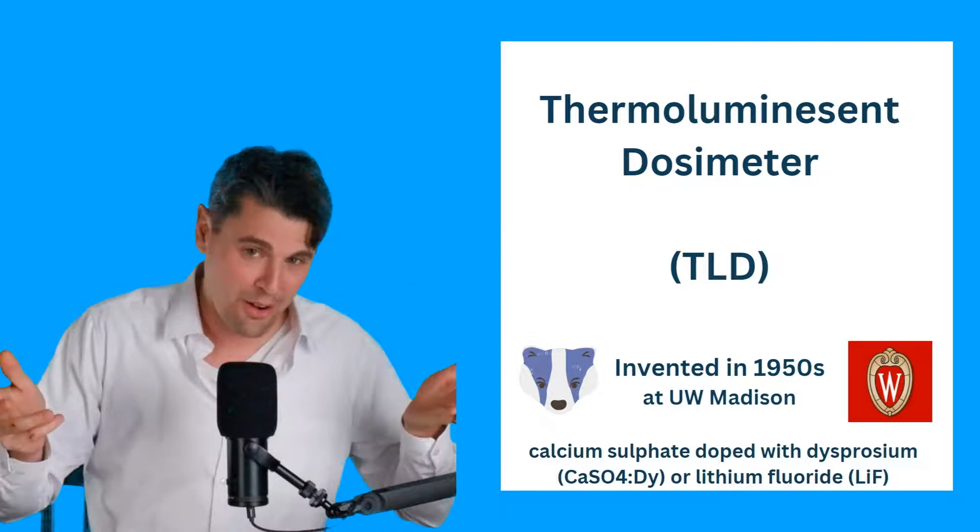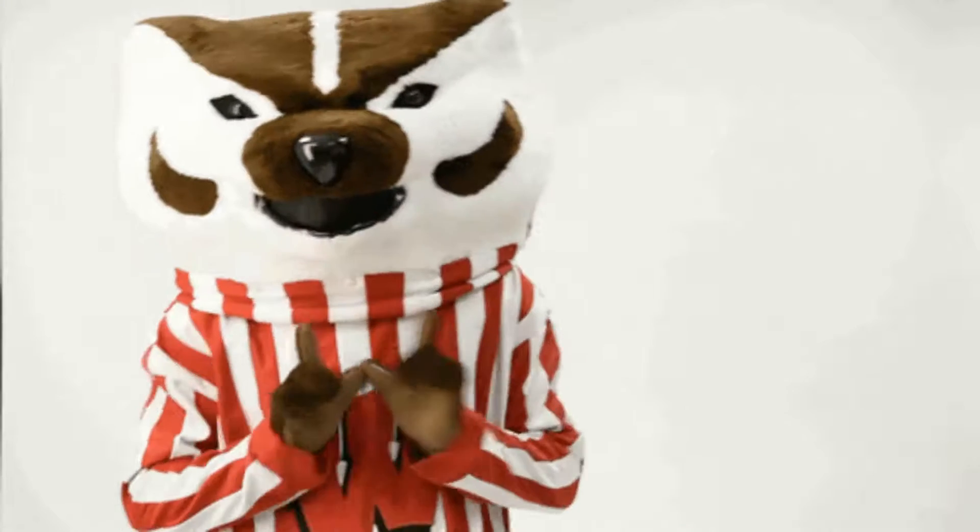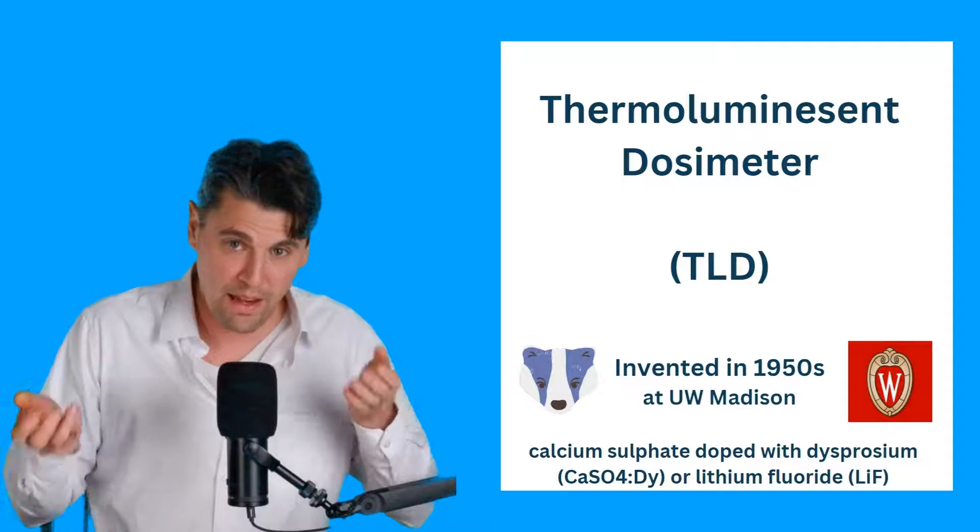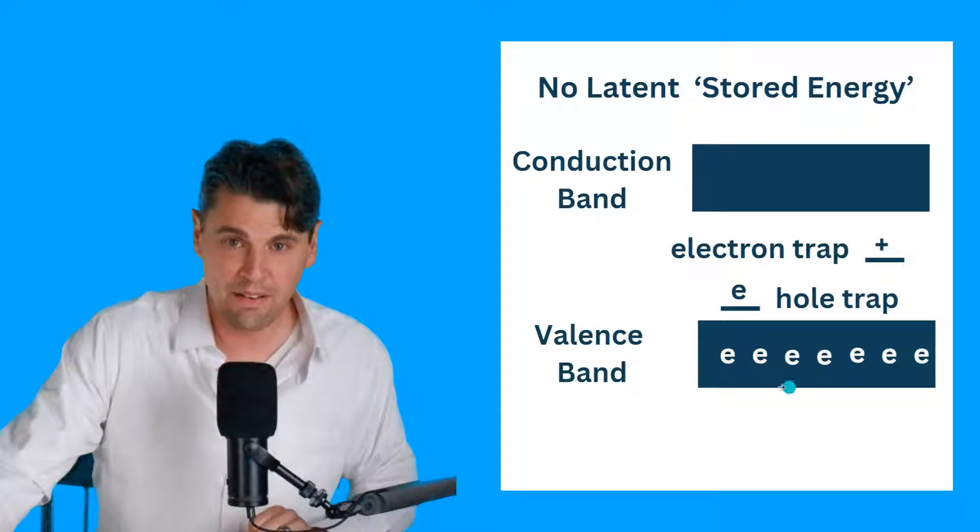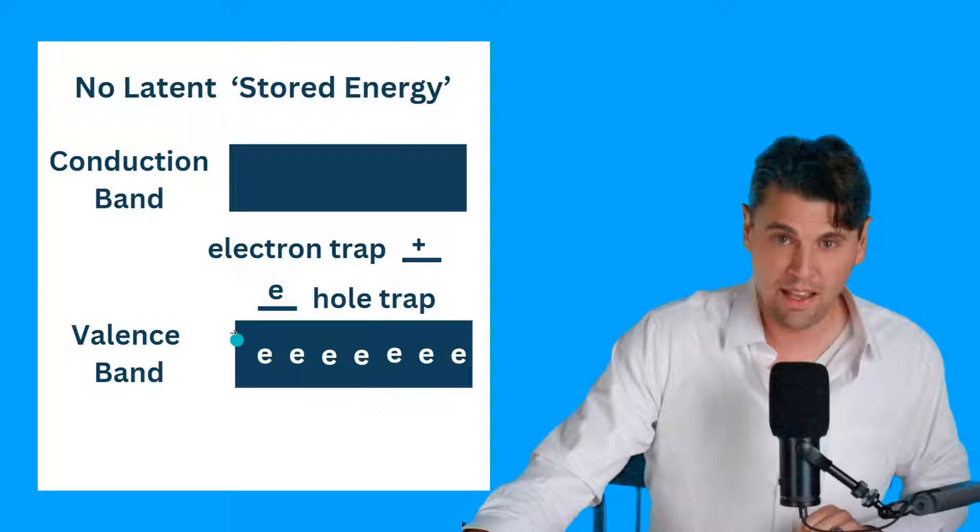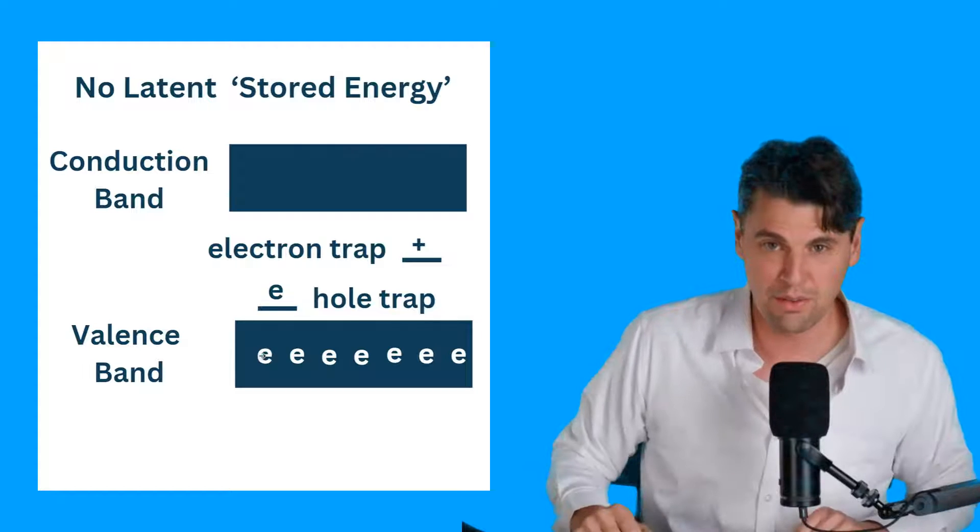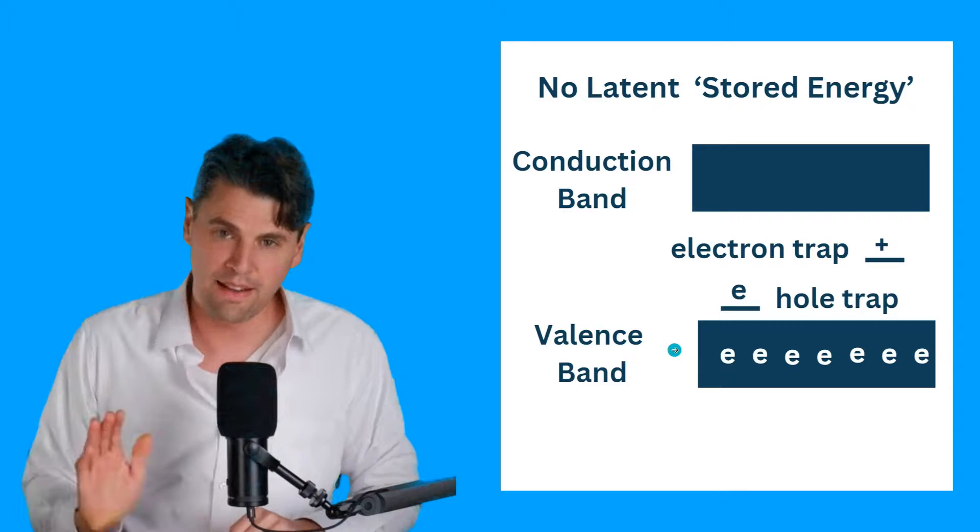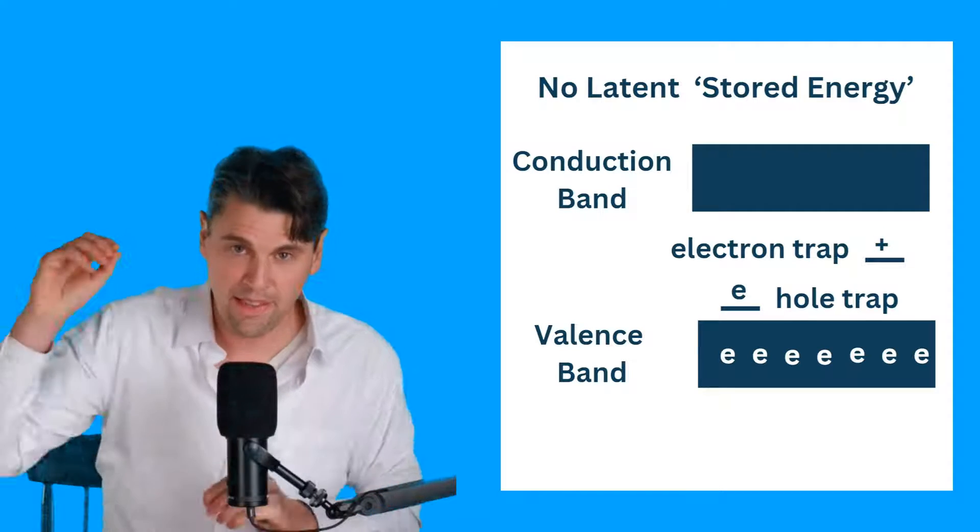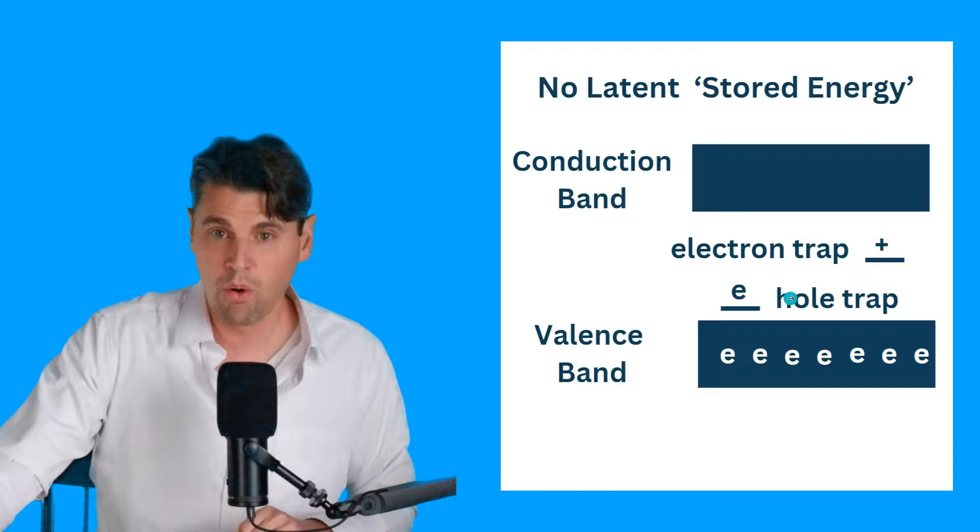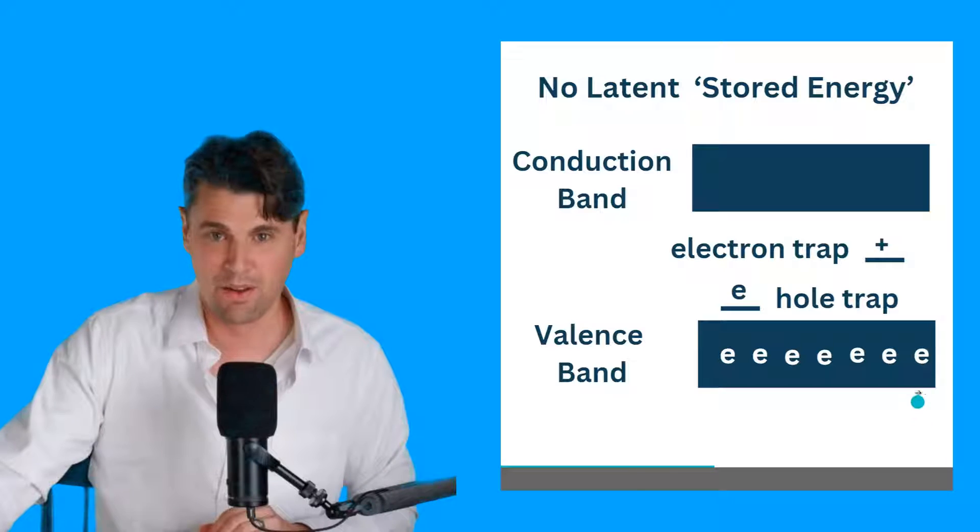You know, I went to University of Wisconsin-Madison. So I always love to point out the fact when things were developed there. And TLDs were actually developed in the 50s at University of Wisconsin-Madison. It could be either calcium sulfate or lithium fluoride, for instance. And in those actual materials, you can think of having a valence band and a conduction band. And in that valence band, you have lots of electrons hanging out here. And then in that conduction band, you have fewer electrons hanging out here. But the electrons can get to that conduction band. And we talk about having the ability to trap electrons. The idea is that higher in this little plot here means it has a higher energy. So if you can get an electron up there in that trap, that electron is going to be trapped with a higher energy. Likewise, a hole or an absence of electron, you could get to a higher energy than this valence band, where all these electrons are hanging out. So right off the bat, we say there's no latent energy stored in this state, where there's not actually an electron trapped yet in an electron trap.